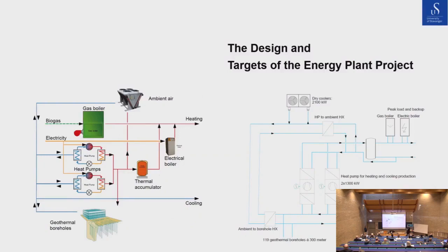Here are two different system sketches. Basically, there are two heat pumps. They are the heart of the system. They have been designed to meet the cooling demands of 3 megawatts. They interact with 119 geothermal boreholes, shallow, 300 meters, but also ambient air coolers, and I'll come back to why that's a bit interesting. Additionally, there are peak load heaters and boilers, and everything works together in an integrated system.